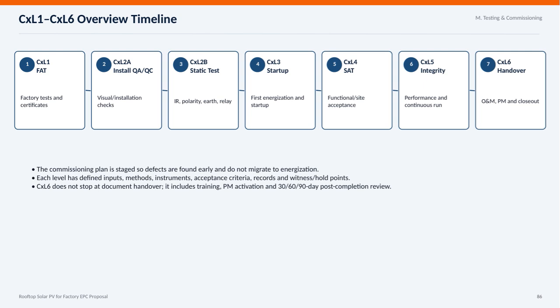CXL4 is the site acceptance testing, confirming that the system performs functionally in its actual environment. At CXL5, we evaluate the system's integrity by monitoring performance and continuous operation to verify reliability. Finally, CXL6 covers handover, which is more than just document transfer. It includes training, preventive maintenance activation, and a thorough 30, 60, and 90-day post-completion review. This staged commissioning plan is designed so defects are identified early, preventing issues from progressing to later stages. Each level has clear inputs, methods, acceptance criteria, and witness points, ensuring a rigorous, structured process.